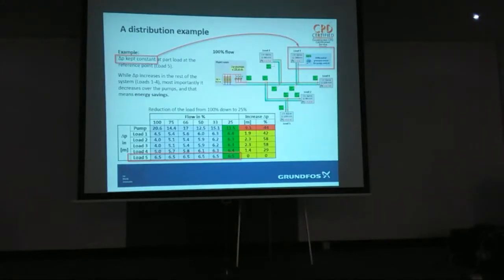On something like this, these could have plate heat exchangers here with their own little circuits, but if you have a central pumping station, this sort of thing can happen. And the increase in pressure at the pump, we can lose up to 44%, but on the local one it could be as much as 58% increase in pressure. Okay, is that reasonably clear? My first time just glazed over. I still do. Looking through these glasses, you glaze over.